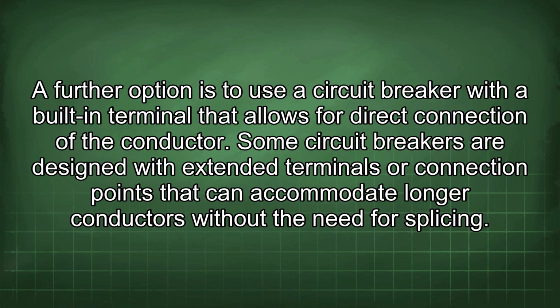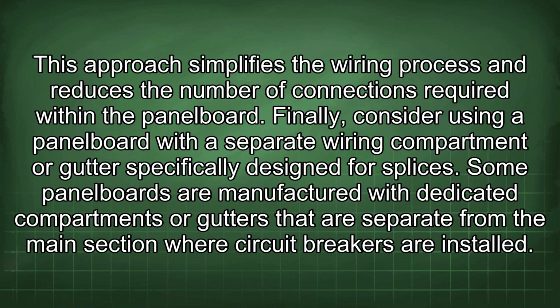A further option is to use a circuit breaker with a built-in terminal that allows for direct connection of the conductor. Some circuit breakers are designed with extended terminals or connection points that can accommodate longer conductors without the need for splicing. This approach simplifies the wiring process and reduces the number of connections required within the panelboard.